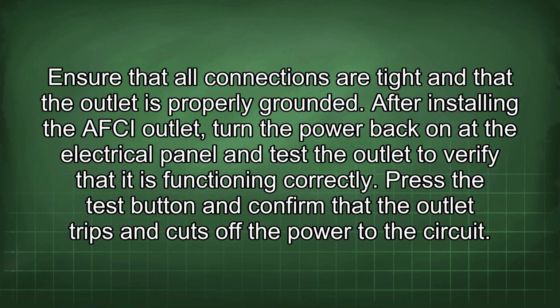After installing the AFCI outlet, turn the power back on at the electrical panel and test the outlet to verify that it is functioning correctly. Press the test button and confirm that the outlet trips and cuts off the power to the circuit.